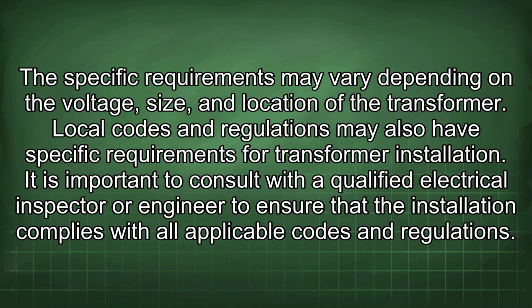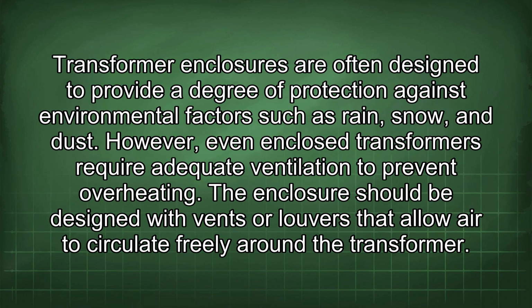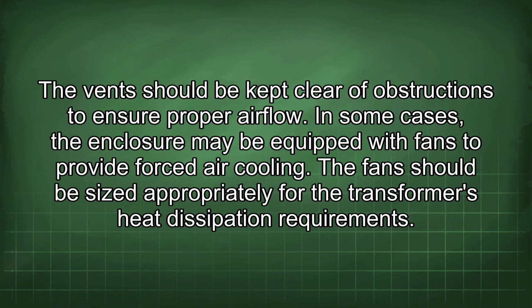Transformer enclosures are often designed to provide a degree of protection against environmental factors such as rain, snow, and dust. However, even enclosed transformers require adequate ventilation to prevent overheating. The enclosure should be designed with vents or louvers that allow air to circulate freely around the transformer. The vents should be kept clear of obstructions to ensure proper airflow. In some cases, the enclosure may be equipped with fans to provide forced air cooling. Fans should be sized appropriately for the transformer's heat dissipation requirements.